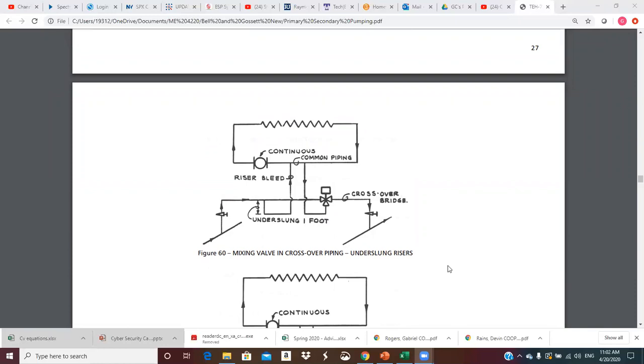It will be noted that the common piping has been moved from its conventional location in the crossover bridge to a new location in the secondary circuit. When I introduce a pressure drop down here, that requires my common pipe to be up here in the secondary — that's a little bit different. The other diagram shows what happens when the actuator is on the bottom of the valve instead, which adds the flow control valve.